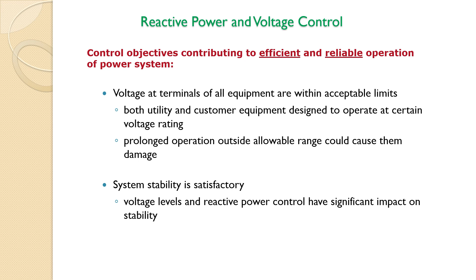For example, overhead lines. Depending upon the load current, they can either absorb or supply the reactive power. At loads below the natural load, that is the surge impedance loading, the line will produce a net reactive power, and at loads above the natural load, the line will absorb the reactive power.